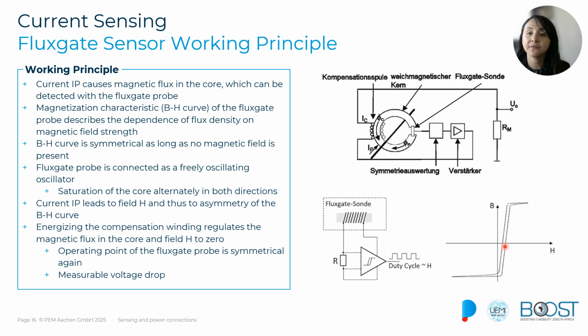However, when we have a current flowing through it, it will induce an external magnetic field, and that induced field will cause an asymmetry in the curve that we are trying to detect. The sensor measures the voltage required to achieve balance and restore symmetrical magnetization in the core, and that voltage is directly proportional to the current flowing through our conductor.